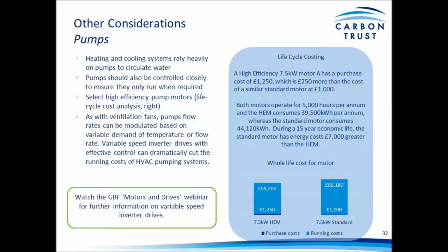This particular pump, for an extra expenditure of £250 when purchasing, pays back £7,000 over the lifetime of the pump just by purchasing the higher efficiency alternative. So it's a very worthwhile investment. Flow rates, as with fans, can modulate based on demand, and variable speed inverter drives with effective control can dramatically cut the running costs of a water pumping system. Again, I would encourage you to watch the Motors and Drives webinar for further information on how variable speed drives can be implemented and affect energy savings within your heating system.